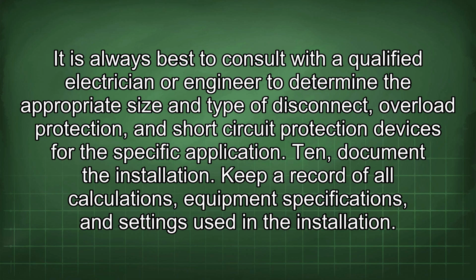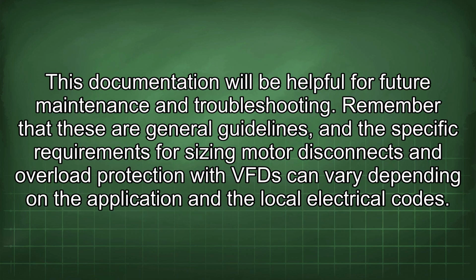Tenth, document the installation. Keep a record of all calculations, equipment specifications, and settings used in the installation. This documentation will be helpful for future maintenance and troubleshooting. Remember that these are general guidelines, and the specific requirements for sizing motor disconnects and overload protection with a VFD can vary depending on the application and the local electrical codes.